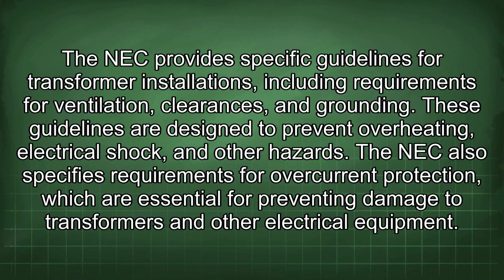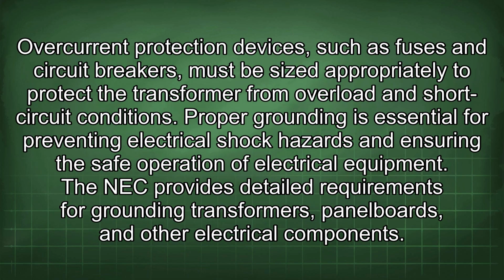The NEC provides specific guidelines for transformer installations, including requirements for ventilation, clearances, and grounding. These guidelines are designed to prevent overheating, electrical shock, and other hazards. The NEC also specifies requirements for overcurrent protection, which are essential for preventing damage to transformers and other electrical equipment.